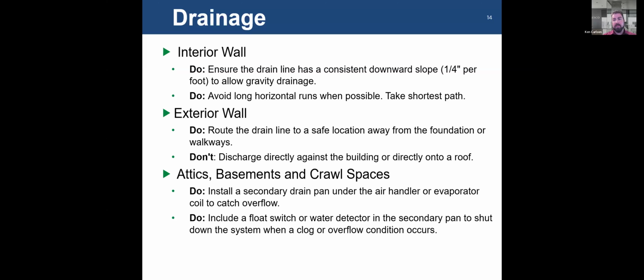At some point throughout the life of that equipment, it is very likely that that drain line is going to clog. You need to have an auxiliary pan to catch that condensate, or you could end up with a mess. In that auxiliary pan, that secondary pan, should be a float switch or water detector, something for you to understand or indicate that you're in an overflow condition. Something needs to be done. A lot of times the float switch is hardwired into the unit. It'll shut the entire system down, or at least the air conditioning down. You have a problem. It prompts somebody to actually go take a look and address the situation.